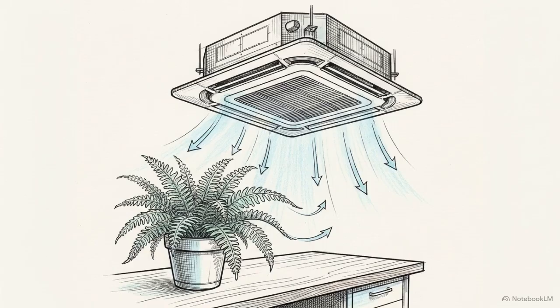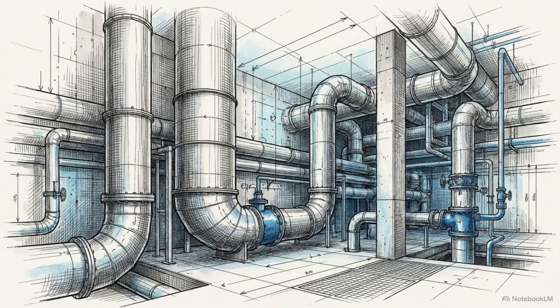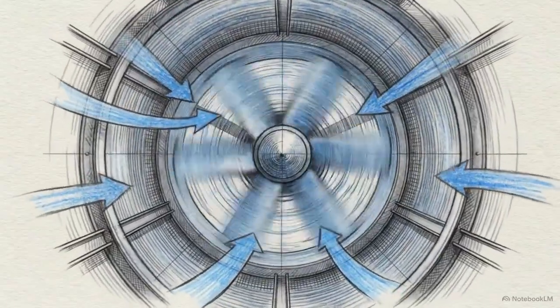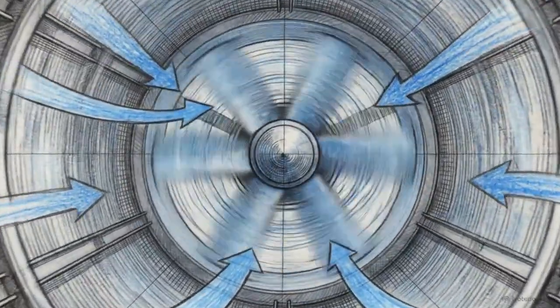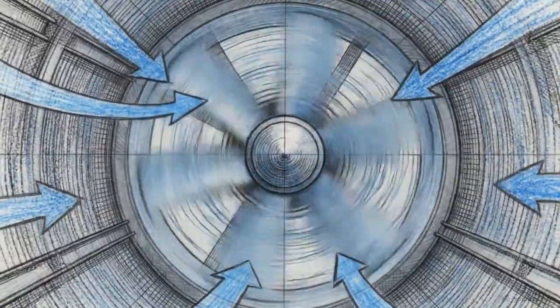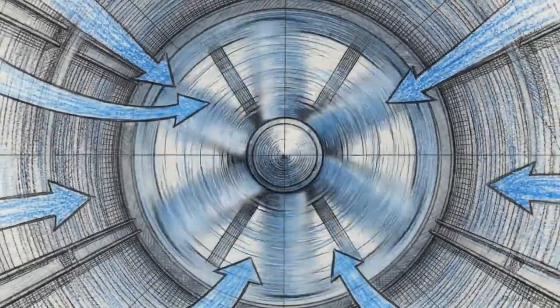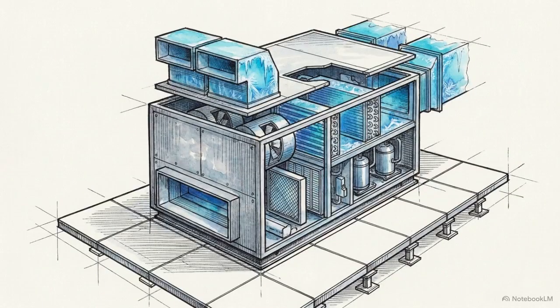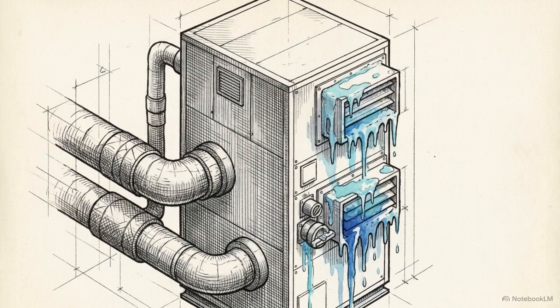A standard office building just needs a gentle breeze to keep humans comfortable. A high-density data center requires extreme, continuous thermal extraction. To prevent equipment failure, facilities rely on raw industrial scale, pumping massive volumes of frigid air through the complex every single second. The baseline defense utilizes massive mechanical systems, CRAC units, which stands for Computer Room Air Conditioning, and CRAH, or Computer Room Air Handlers.